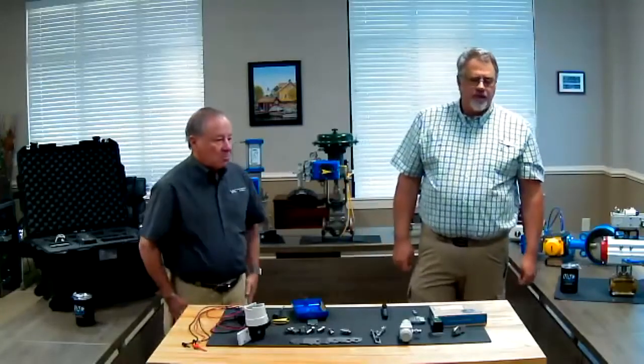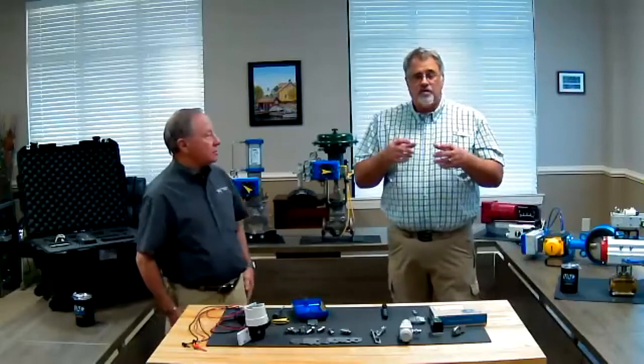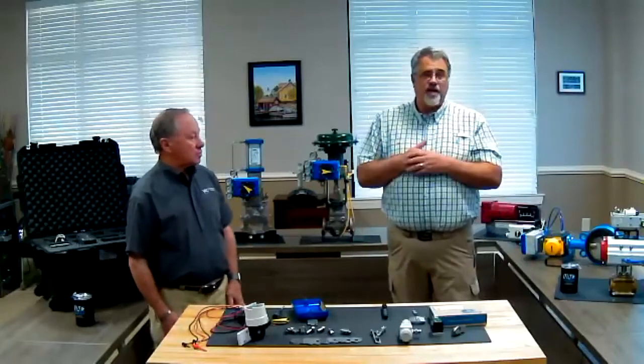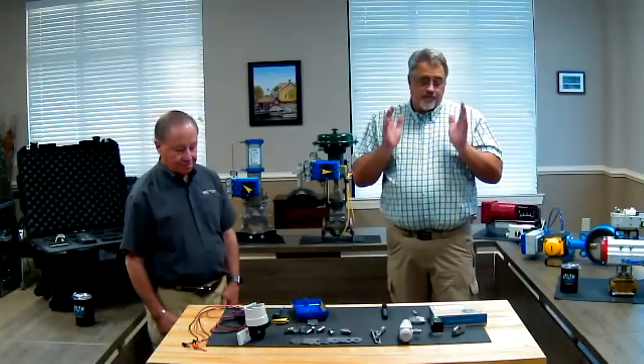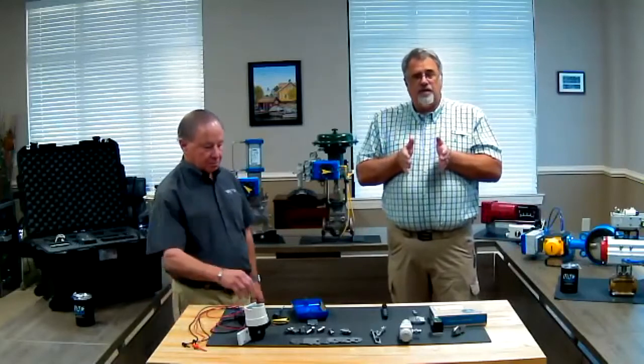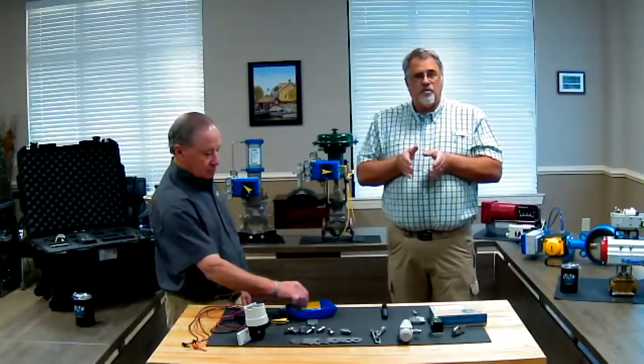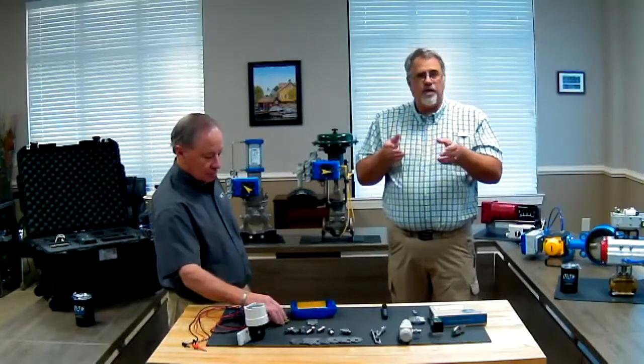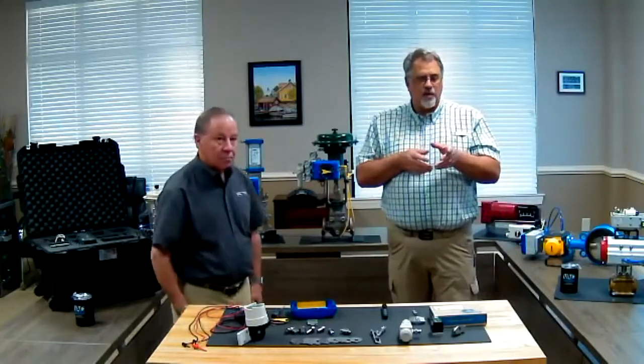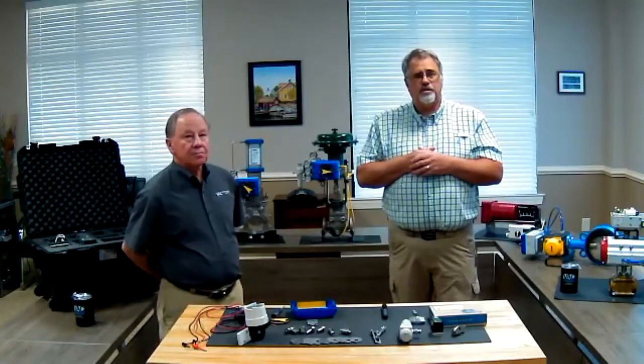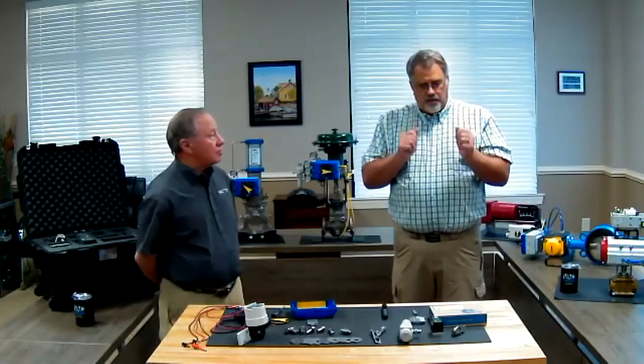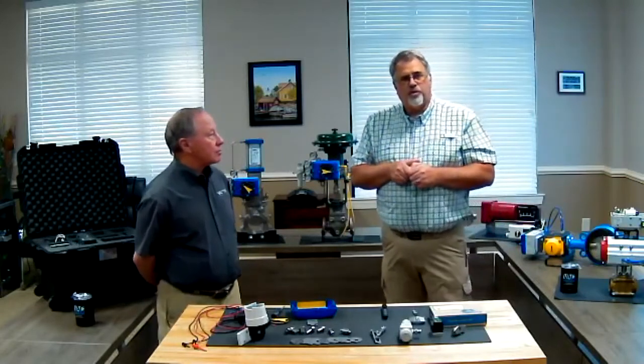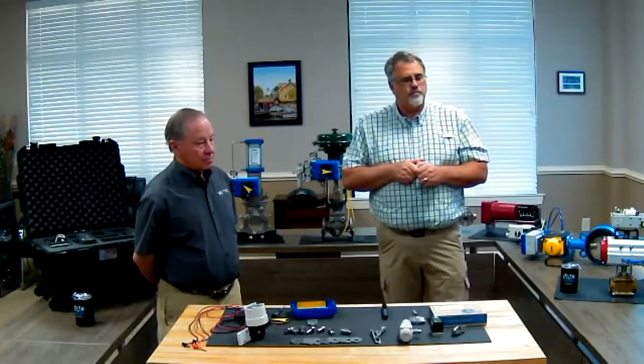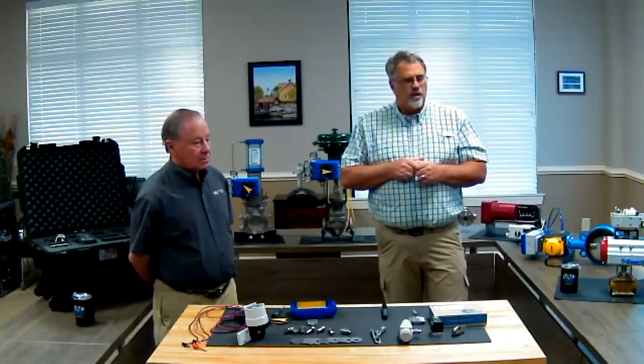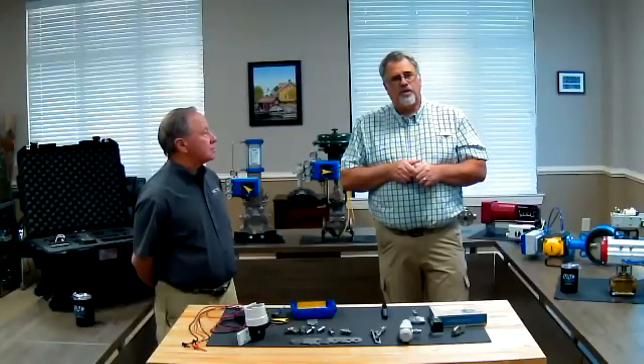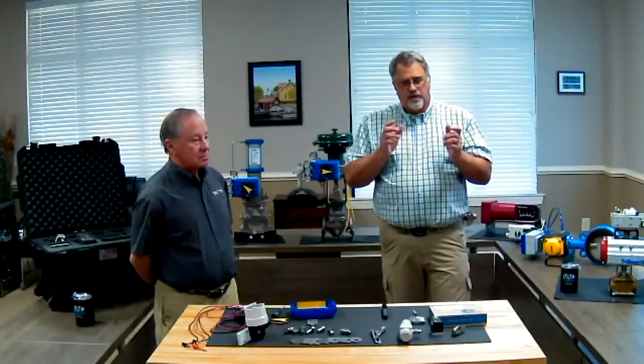Absolutely, in fact that's the point, is that you don't have to take the positioner off, you don't have to take the valve out of line. You can do that if it's already not working because they've had a failure, you can get it up and running without taking anything out, doing a line break and all of that sort of thing. Worst case, you've got a hot work permit for working with electrical wires, and you can do this in place in a very, very short period of time. We have plants with hundreds and thousands of positioners installed in them that do just that.